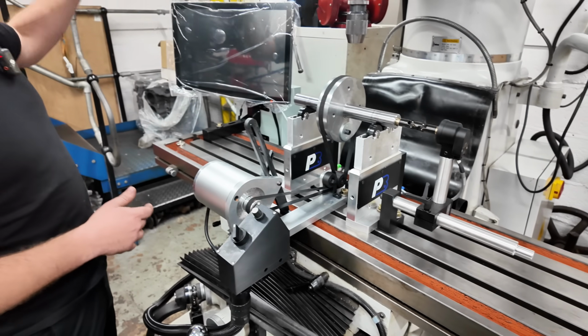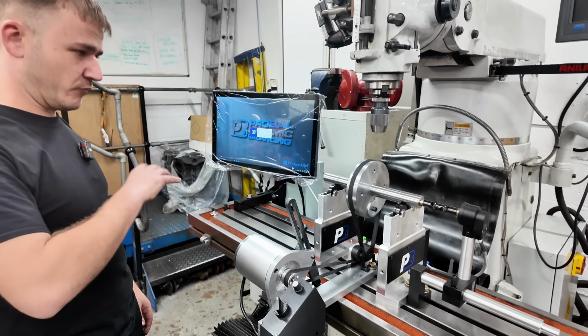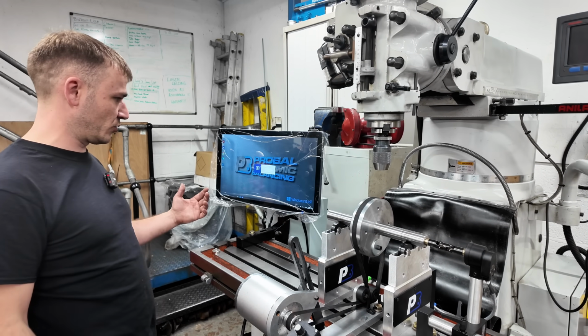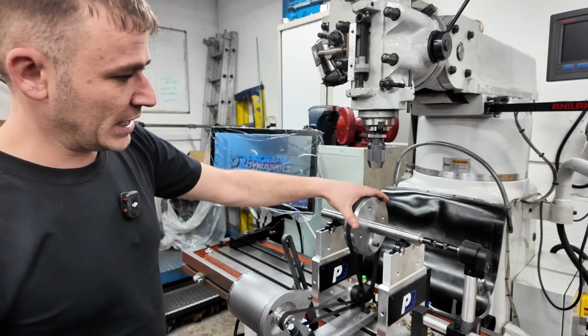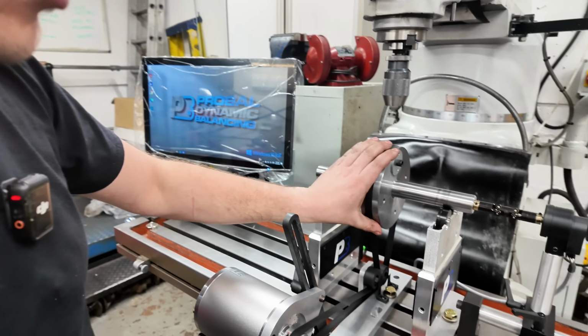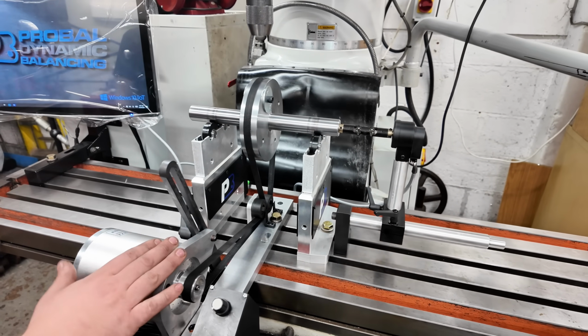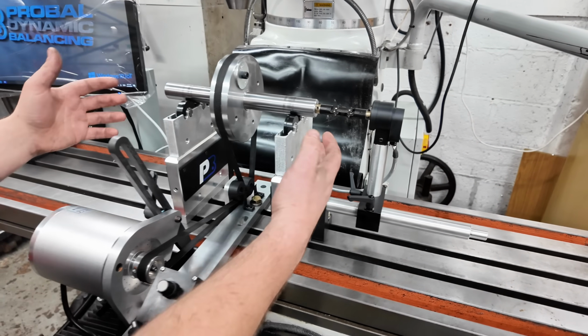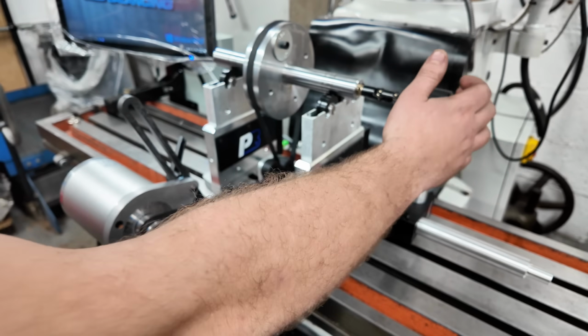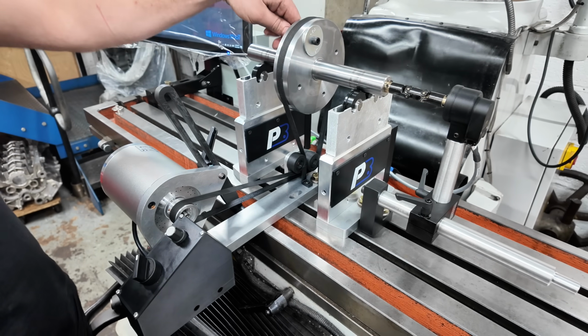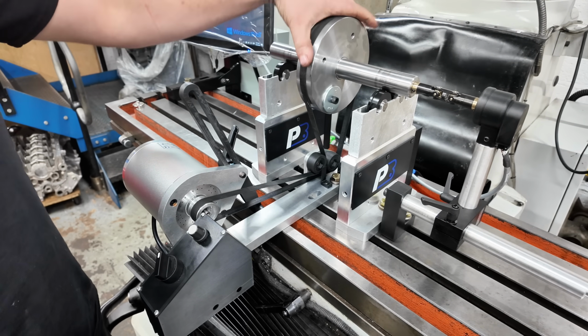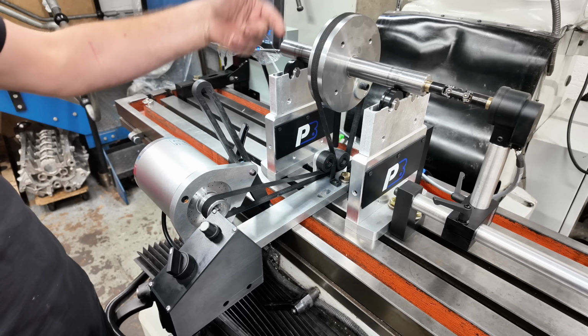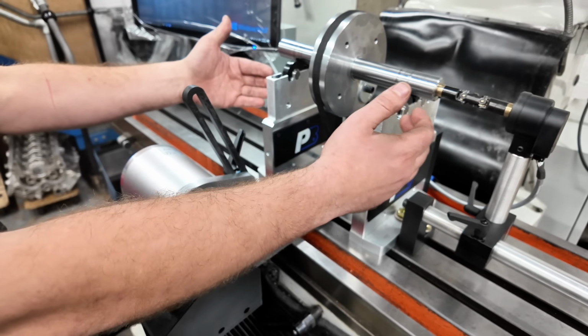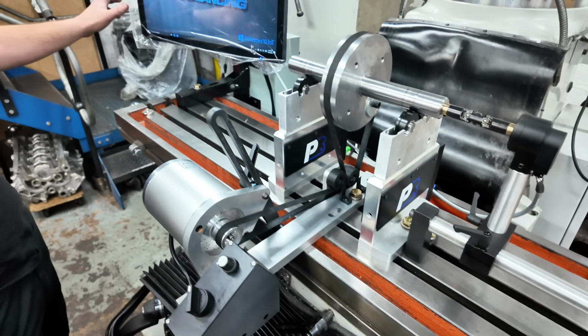So what we're going to do, turn it on for the first time. Me and Ross have set this up so that we can sort of go through this. And basically this is your calibration arbor. So how the machine works, you have a motor and a belt, turn it, 2 sensors and an encoder. So that encoder should tell us where the crankshaft is, how fast the crankshaft is spinning, or the test piece currently here, and then the sensors will read 2 measurements.